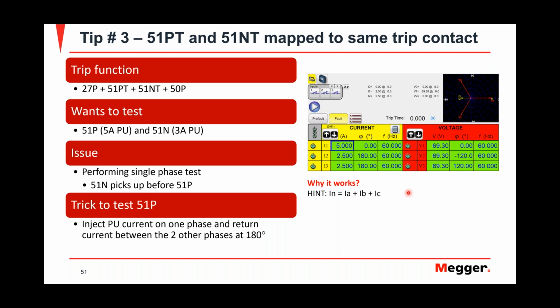It will allow you to test that quicker instead of disabling this 51N protection to test the phase protections. This is one tip that you could use. And why does it work? Well, the hint is your neutral current is the vectorial sum of all these. And when you sum all that, you get 0. And that's why it works.